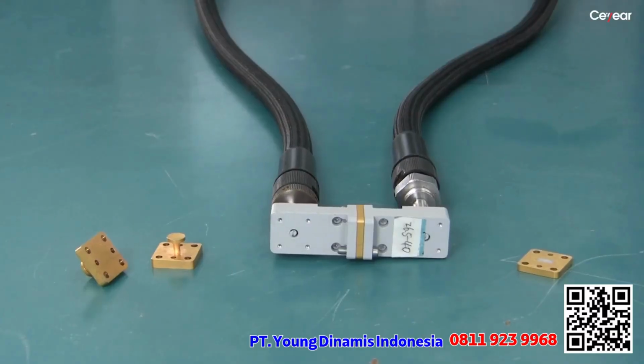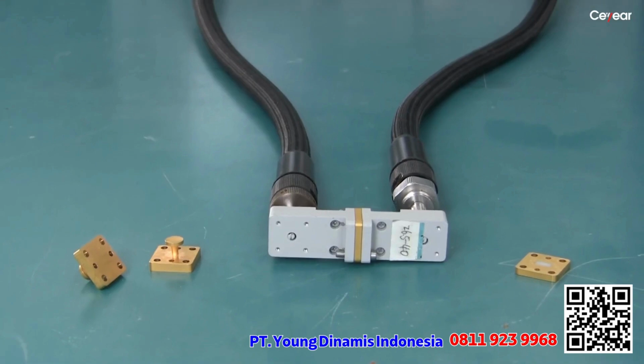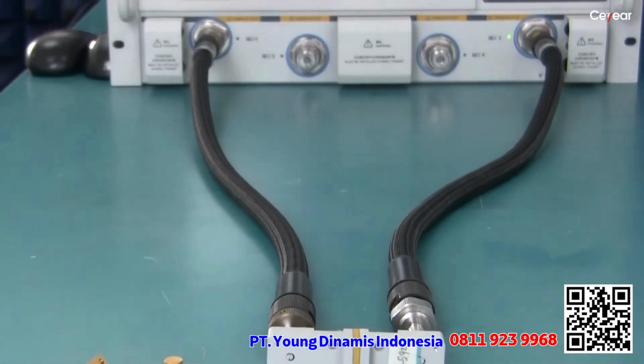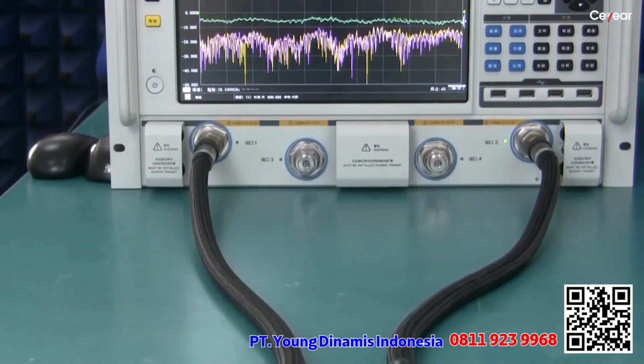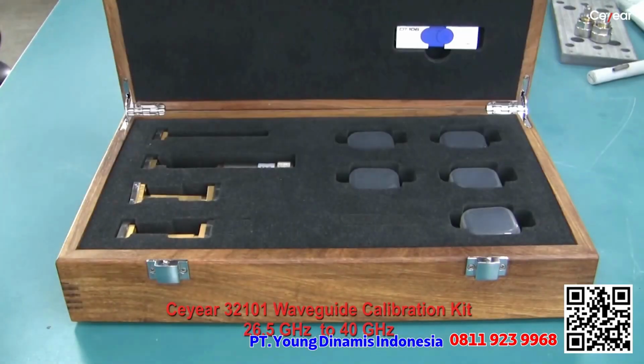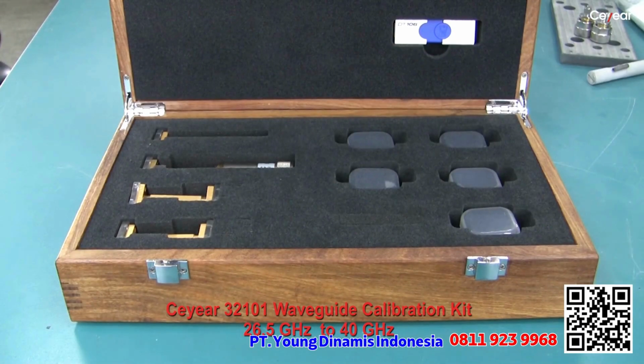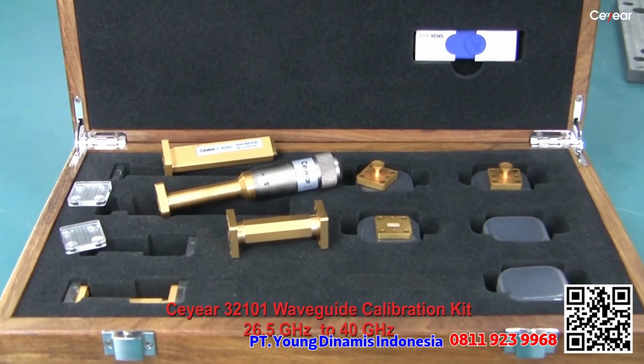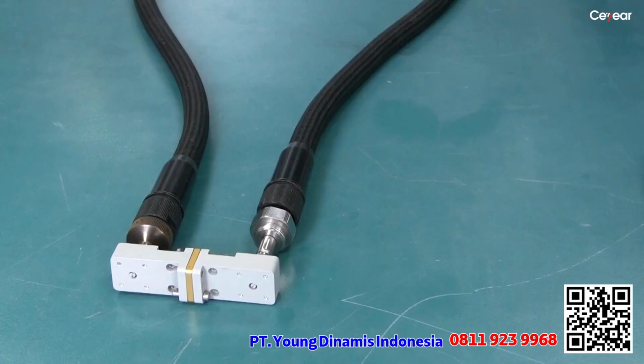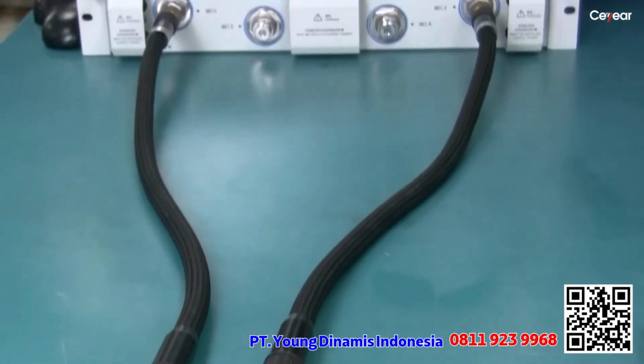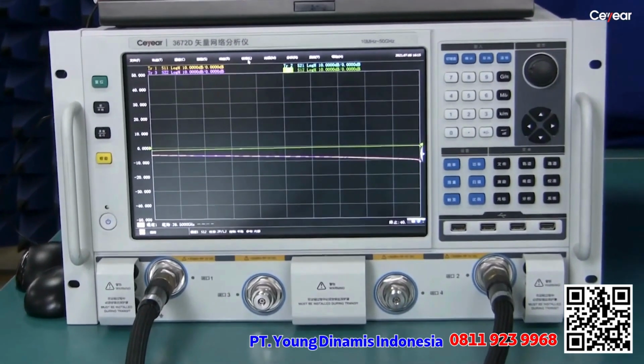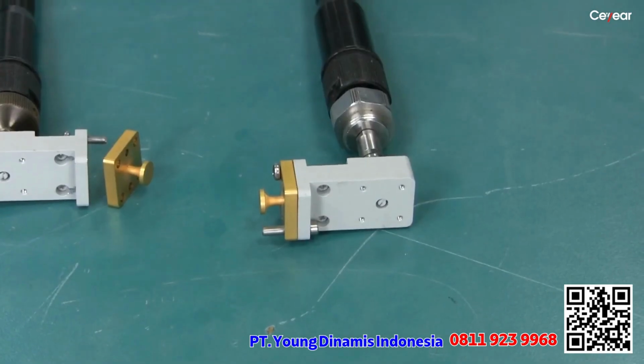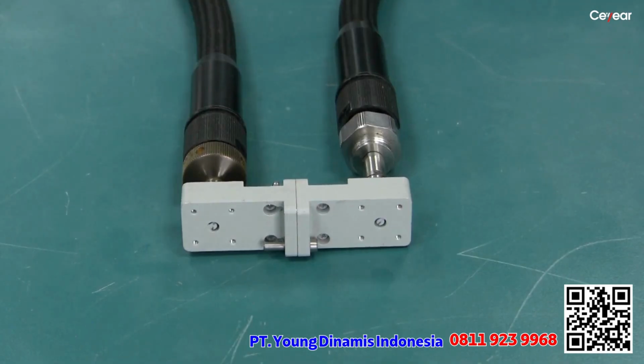Now we can use another smaller transmission line to make a 26.5 GHz to 40 GHz test. We use this calibration kit to make the VNA calibration and also use each 1/4 wavelength offset waveguide to hold the material and test. Firstly, we follow the calibration wizard to make a short offset through calibration.